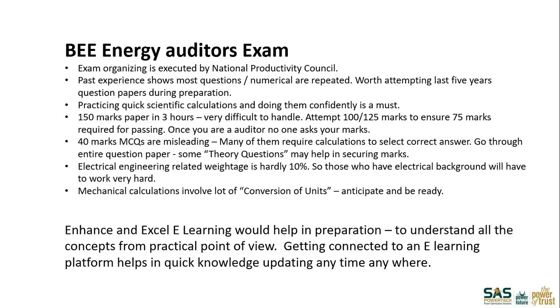Fundamentally, this course and overall energy auditing concentrate more on mechanical equipment because almost all mechanical equipment have a very narrow best efficiency band during operation. If you take a pump for a typical head and flow, maybe 20% less or 20% more will give you best efficiency. That doesn't happen with electrical equipment - a transformer's efficiency from 10% to 100% load may only vary from 95% to 98%, it will never go down to 10% or 12%. In my career, I have audited 500 kilowatt pumps working at 23% efficiency - they were consuming full power but delivering only 70% output, because they weren't operating within their best efficiency zones. So there you actually get huge opportunities to recommend improvements to your clients.